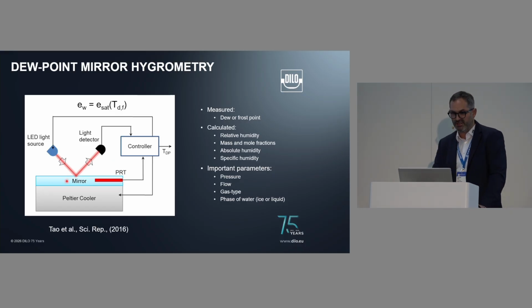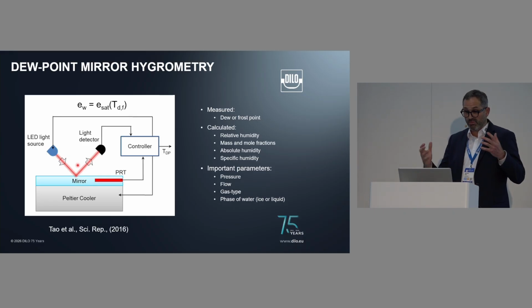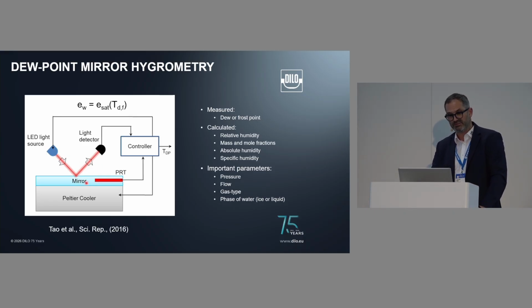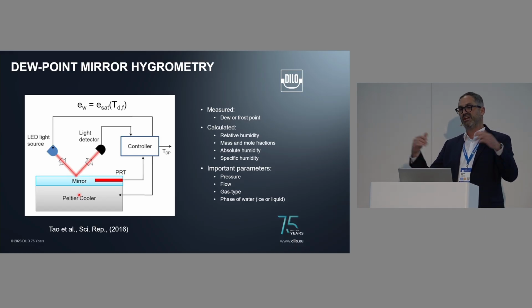We have here a cooler. We have here a mirror, which has a very flat, clean, reflective surface. And in that mirror, we have a temperature sensor, and then we have an LED, which illuminates the surface. The surface reflects, and the reflection value is detected by a photodiode, a light detector in general. And now you can imagine if you have a flow from the left to the right, for example, of humid gas, and the mirror starts to cool, and it cools until a point where condensation sets in.